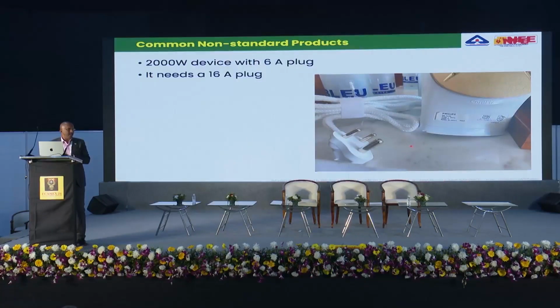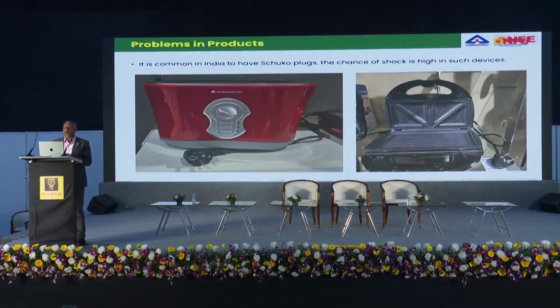Second item, second photo, what you are seeing is an iron box. It's a 2000 watts iron box with a 6 amps plug. Any electrical apparatus more than 1000 watts should have a 16 amps plug. Whereas this one is 6 amps, where the current is more, you cannot handle it. So such violations are quite common in our country, very, very common. Even the expert electrical engineer will not look into these subjects seriously. For example, if you go to any of the 5-star hotels in Mumbai, every year these 5-star hotels do an electrical safety audit. If you look at the plug and socket which they use for their water heater, the kettle, the iron box, it's a violation, a clear violation.